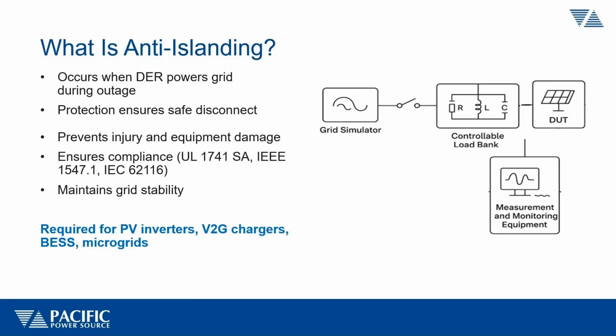Because when there is a power outage, usually the utility obviously sends out a line crew to go and restore power and repair any damage. And when these guys are working on that part of the grid, they expect it to be de-energized, of course, because it's down. If these DERs that are connected, it could be your home PV and solar installation, are still putting power back on that section of the grid, it's extremely dangerous for these line workers. So any PV inverter or any other energy producing device that pushes energy back onto the grid, like a solar inverter or wind inverter, has to meet certain safety criteria having to do with anti-islanding, and it means they need to stop pushing energy on that section of the grid when that happens.